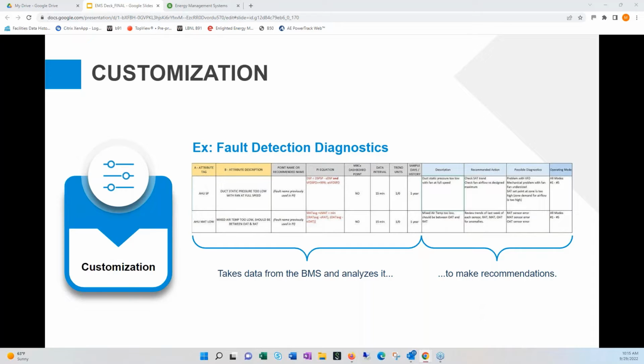We're talking about fault detection diagnostics, or FDDs. In California, they're actually starting to require this on package units. For more customized systems, there's a guideline out there, not yet a code requirement, called ASHRAE Guideline 36. It has a lot of these fault detection diagnostics already pre-built, so they can be easily implemented into a building or an EMS. Let me walk through this example.